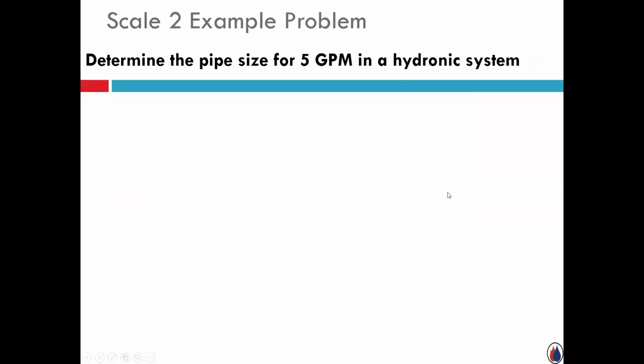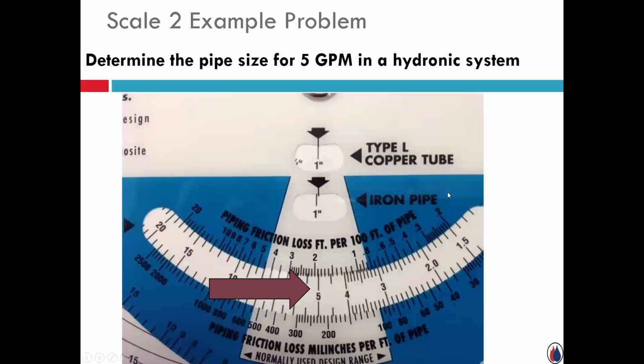In that previous example, we said 100,000 BTUs at that 40-degree delta T. So we increased the delta T, which cut our flow rate in half, in this case, 5. So again, what size pipe? I'm only pumping 5 GPM now. I find it in this white band. The first pipe size that I come across that kind of meets that criteria is 1 inch copper. So same thing, just read it.